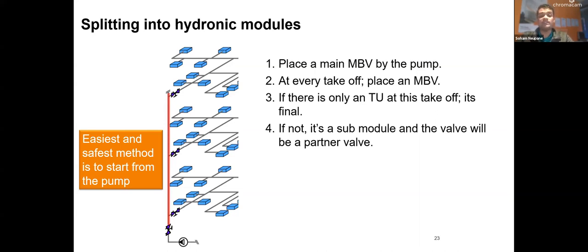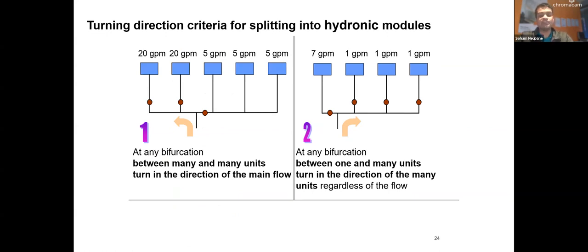So for that, a few things we need to keep in mind is the turning direction when we look at creating hydronic modules. So any kind of bifurcation between many and many units, you want to turn towards the direction of the main flow. So wherever you have high flow, that's where you want to turn. And on any bifurcation between one and many units, so that's one terminal unit on one side and several on the other, you always want to turn towards the side with many terminal units, regardless of the flow. Even though this GPM is higher, I want to go towards where more terminal units are. And that bifurcation, basically, could be your vertical T or horizontal, so that doesn't really matter.